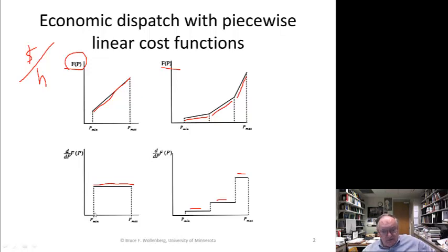The units come on from the minimum, go up to the maximum, then the next unit, then the next unit, so it's very easy to just build a table that tells you what units are generating what, very fast. You don't have to do any lambda search or anything like that.